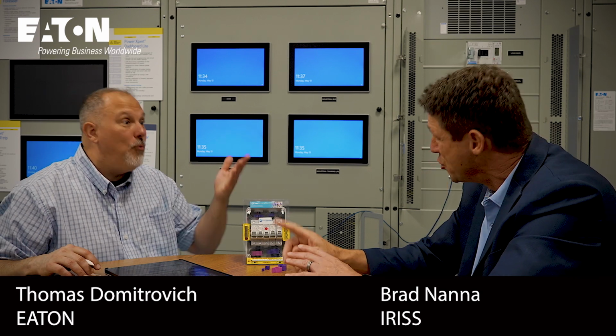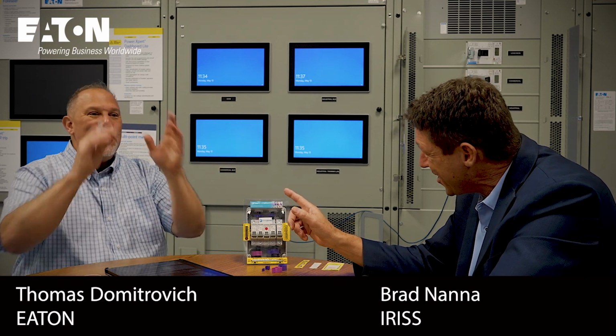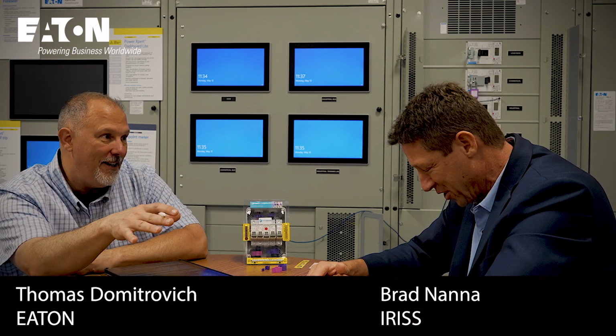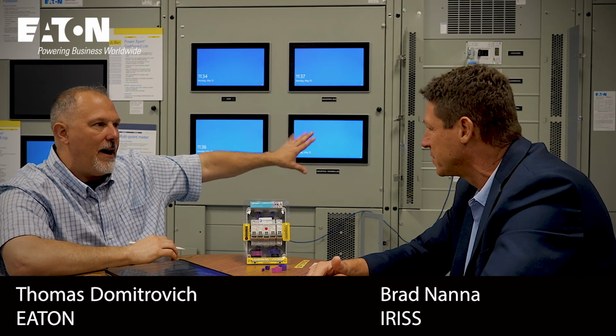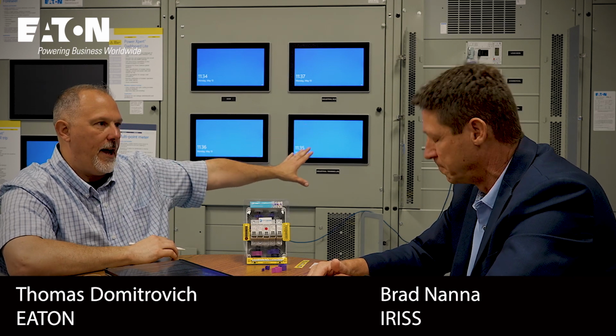You can't if you're removing the panels. To actually do the job, you need to be drawing a certain percentage of current, so you need the equipment energized. Before that, you have to remove the dead front and expose energized parts. That's the definition of justified energized work, because you can't get it done without it being energized, and you do have to expose your electrical workers.